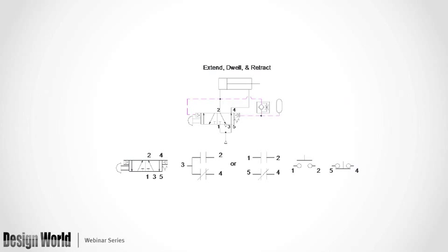Okay, now let's expand a little bit with my circuits. Here I'm using one valve that has the ability to have both a pilot and a push button. And what I've done here is I'm bringing air in ports 1 and 5. Now for you guys that work in pneumatics alone, I don't know if you've ever considered using port 1 and 5 for inputs and putting an air regulator in both port 1 and 5 and use 3 as the exhaust.